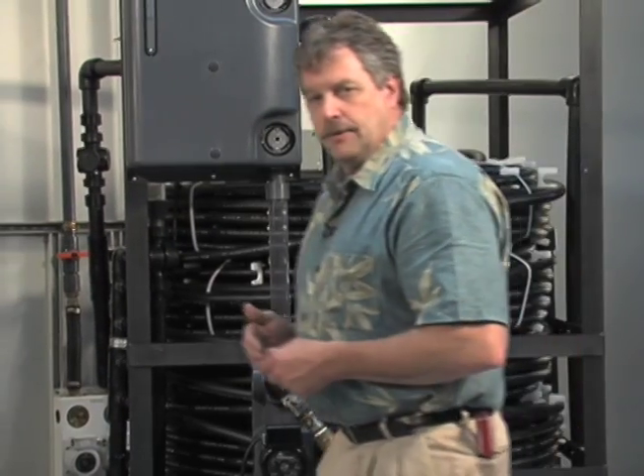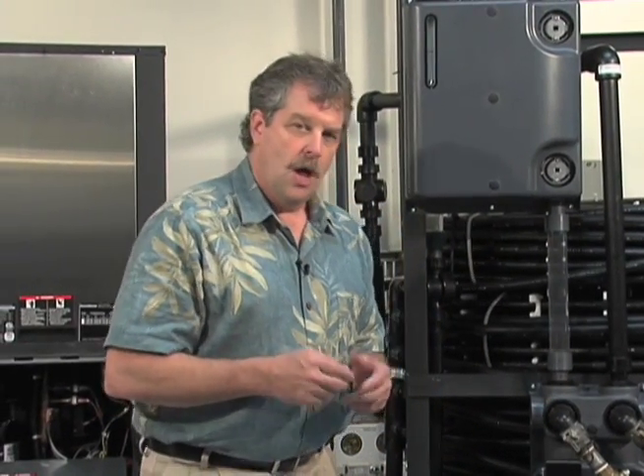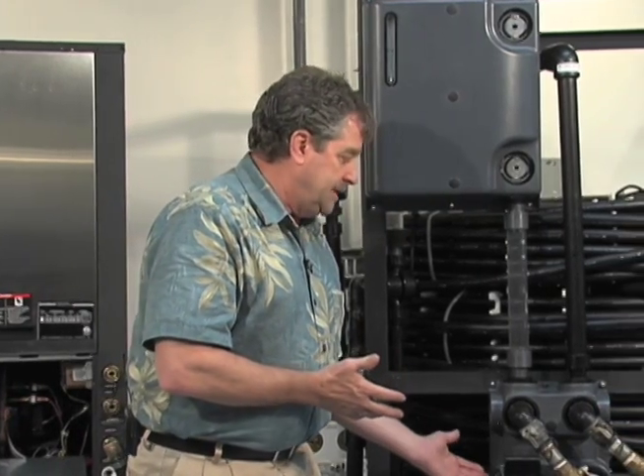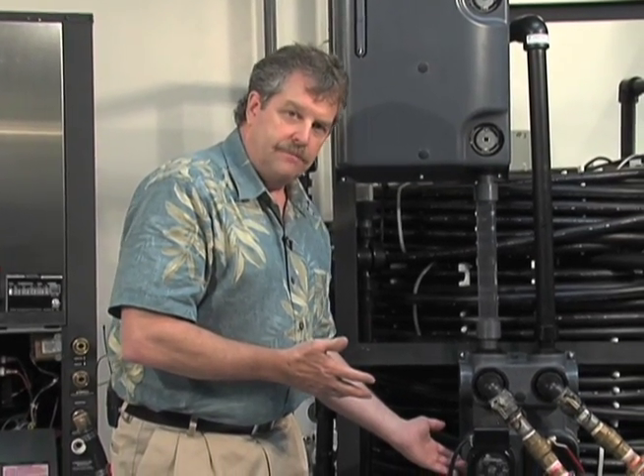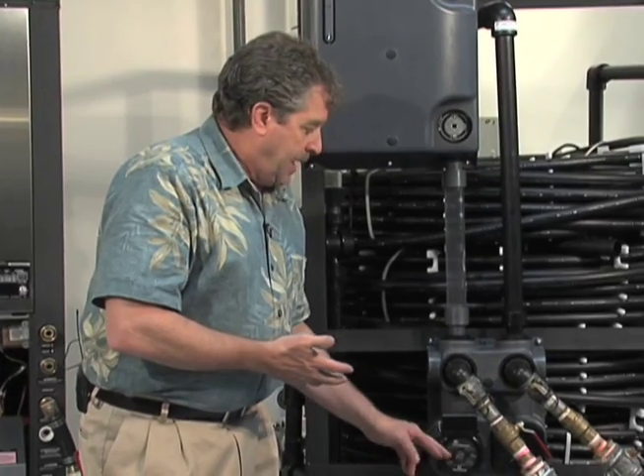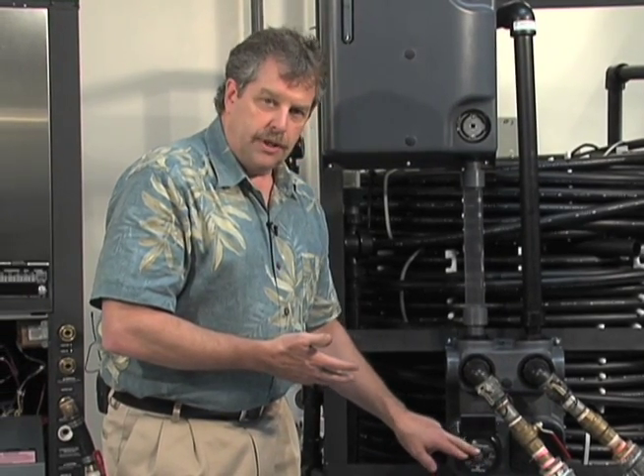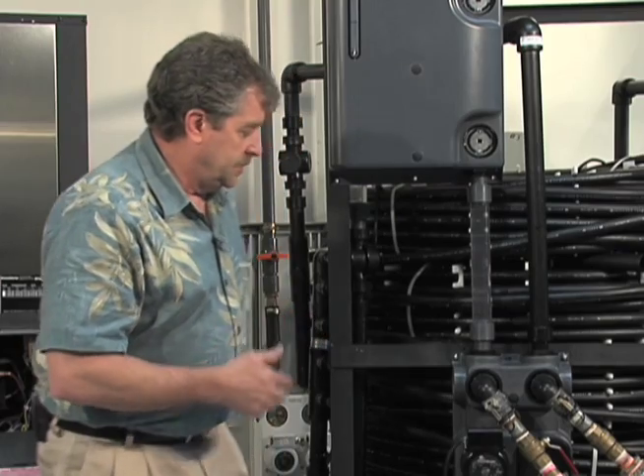So while we have our flush cart pump applying pressure and flushing fluid through the system, an important part that's frequently missed, guys, is you have to actually bleed the shaft of the Grundfos pump. This back bearing is cooled with liquid, and the failure of burping the air out of that means you're going to shorten the life of the pump, snap the shaft, burn the pump up. So it's very important that you do this step.